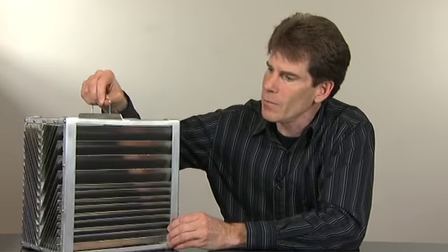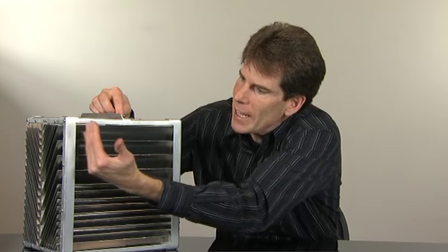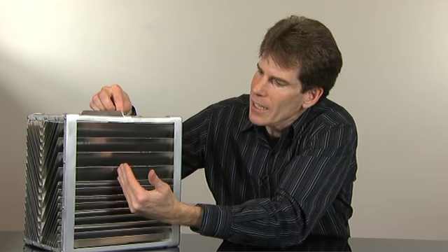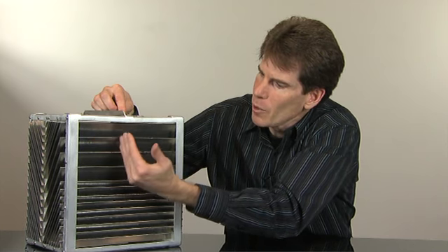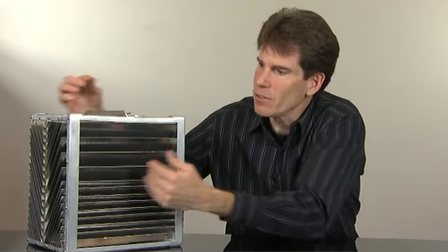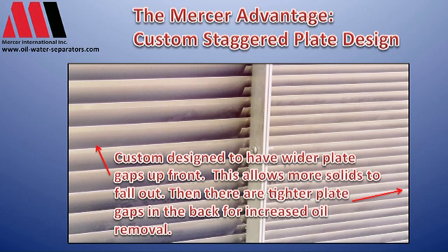The other thing we've done, kind of unique, is we've also built plate pack systems where as the plates go through, we actually can increase the number of plates as you go through the plate pack. So the front of the pack is designed to pull out the heavier solids, and as you drift through the pack with your wastewater, there are more plates in place back here. And by doing that, we can have a very high efficiency and a very low maintenance system that will be good for years to come in the effluent requirement that industry may find.